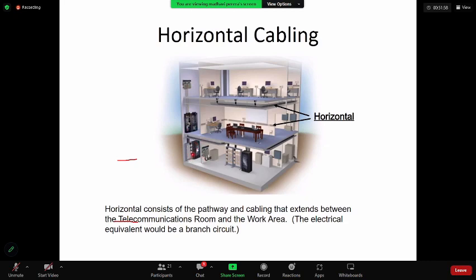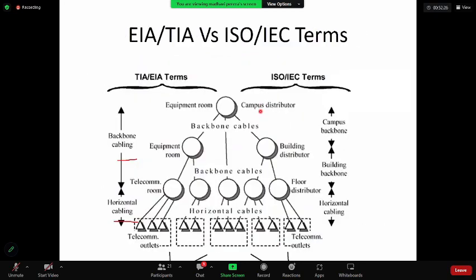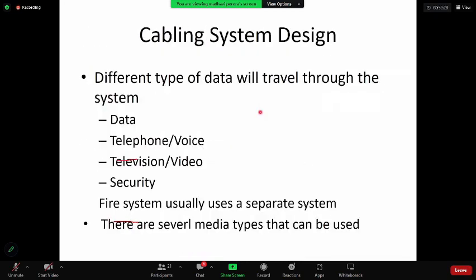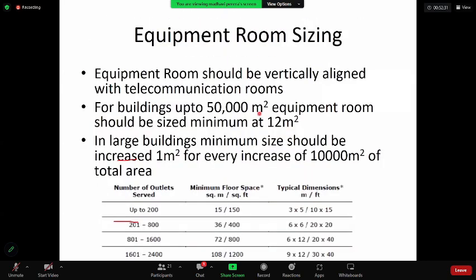If your equipment room is here and you have one telecommunication closet here and another somewhere else, it becomes a very complicated system, so avoid those issues. At the beginning of the building design, you have to allocate space for the equipment room and then plan the telecommunication closets or rooms according to the space required for the floor, in a vertically aligned line. That way, most of your installation issues can be taken care of.